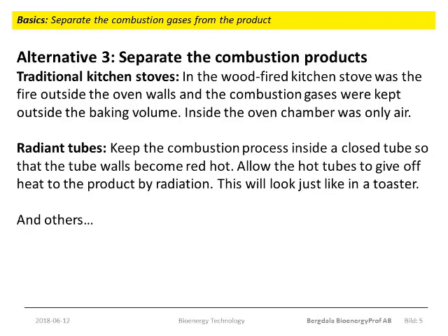One example of an intermediate temperature process where a protective atmosphere is used is the bright annealing of steel. The process runs at about 900 degrees C, and the atmosphere is typically a mixture of hydrogen and nitrogen gas. Electrically heated bell furnaces are often used. But the process could also be run using biogas fired in, say, radiative tubes.